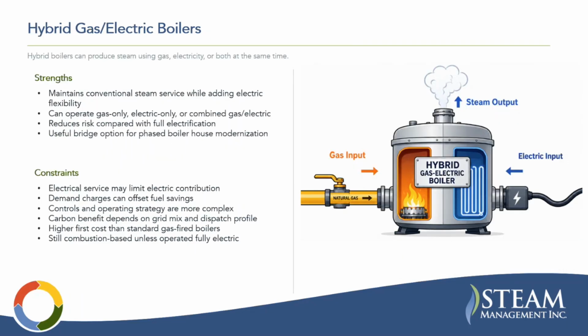Hybrid gas and electric boilers, I would say these are becoming pretty common for moderate sized boilers in Europe. Basically, you have the ability to burn gas to generate heat in the boiler and use electricity. And so you can maintain conventional steam service while adding electric flexibility. Can operate gas only, electric only, or combined gas and electric. It reduces the risk compared with full electrification because you still have the option to burn gas. And I think it could be a useful bridge option for phased boiler house modernization.